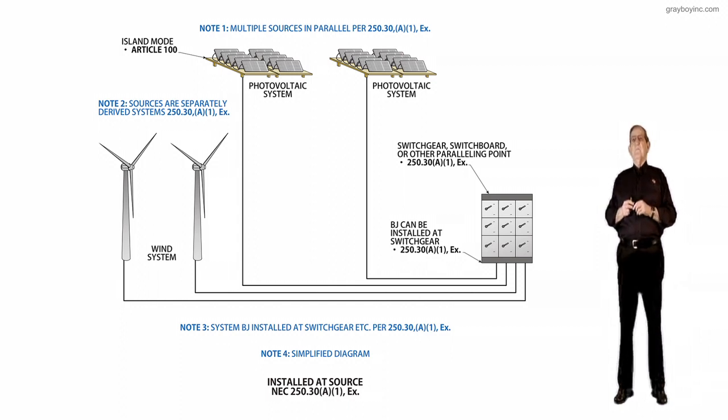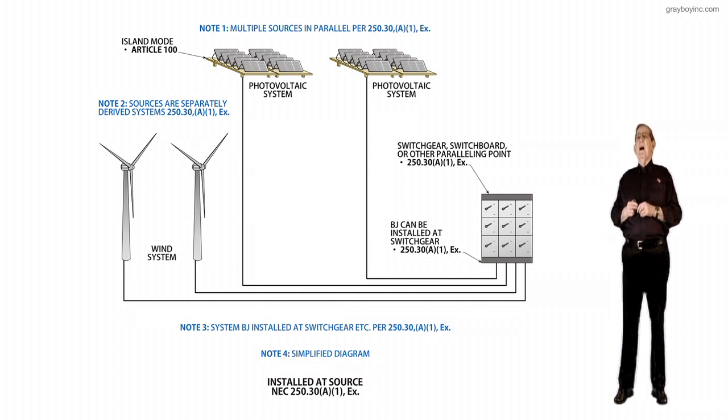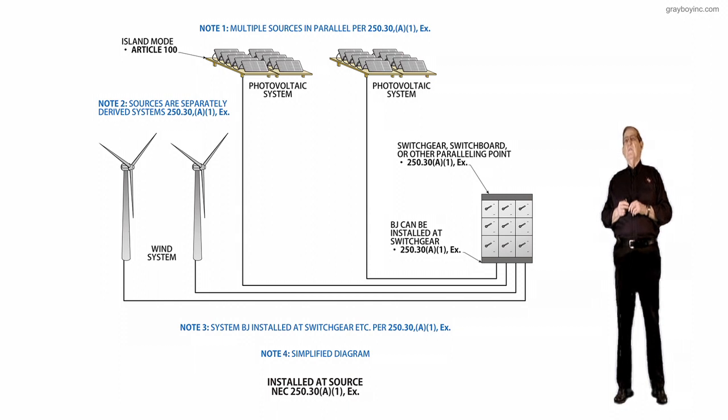That's the only place you pick up these secondary ties that you might have. And then note one, multiple sources in parallel, that's fine, but it's telling you where you can place the bonding jumper to prevent nuisance tripping and signaling and noise. 250.30A1 exception.